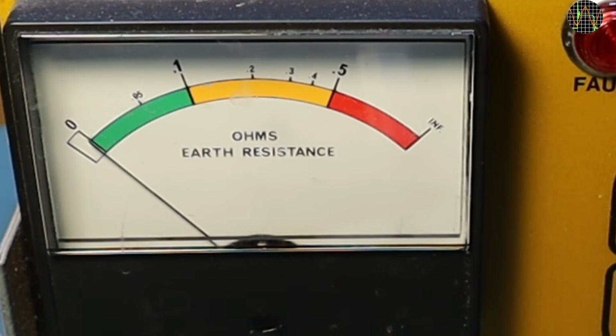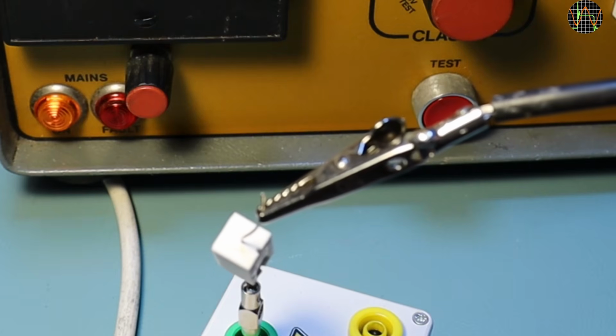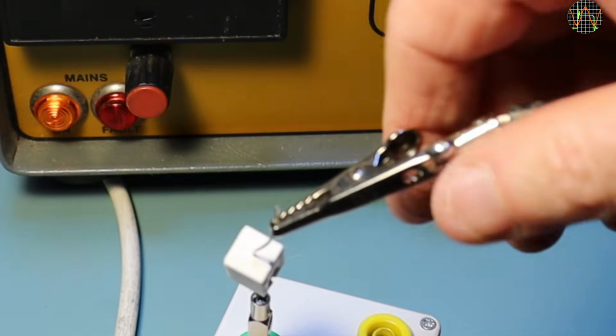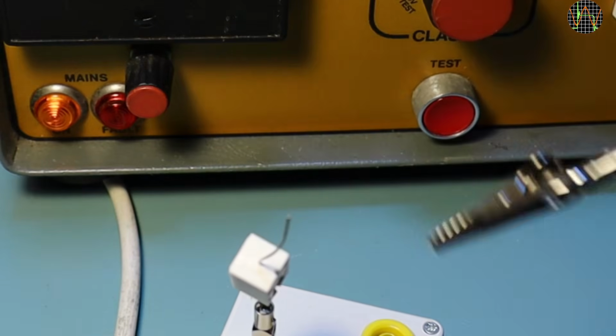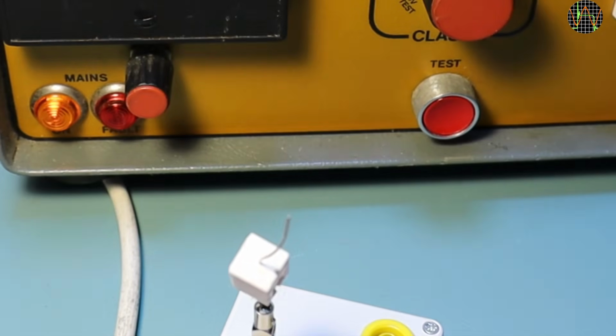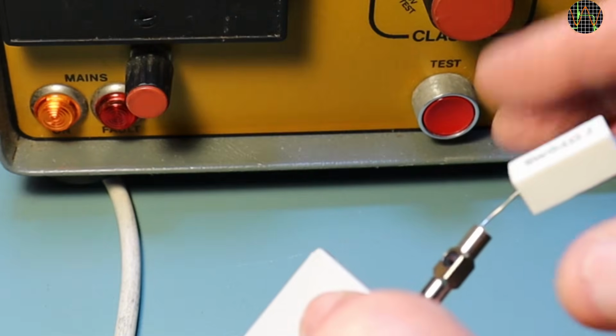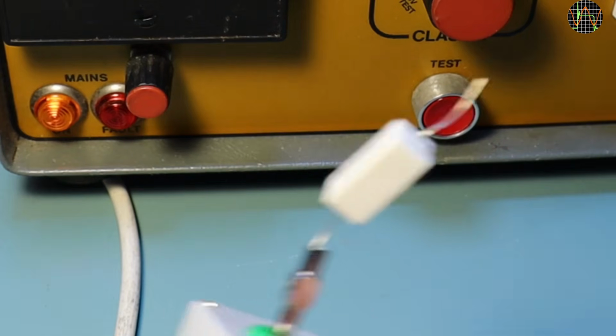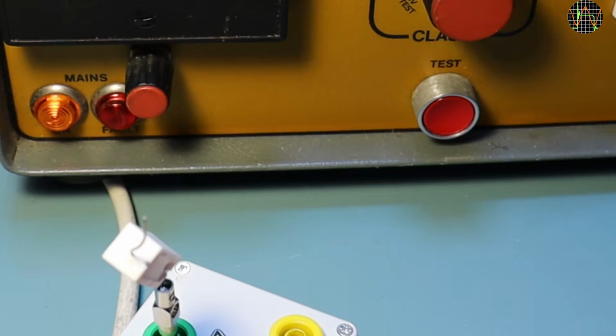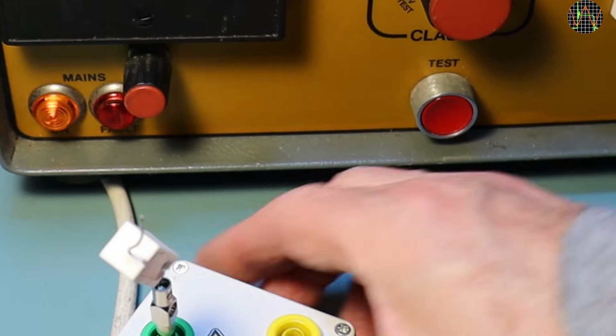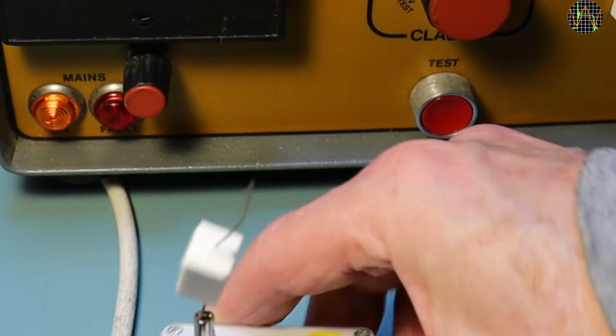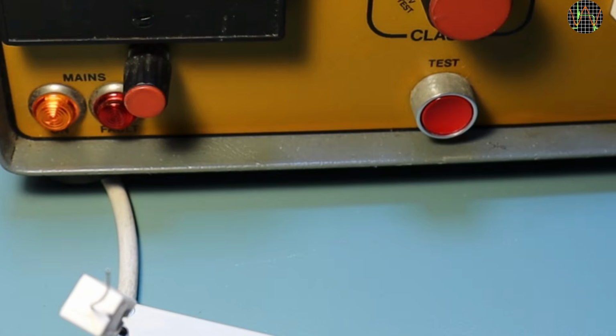But why is this a bad idea? If you would have been in the room, you would have noticed the bad smell of overcooked resistor. That poor 0.1 ohm ceramic resistor is rated for 3 watts. With 32 amps flowing through it, it dropped of course 3.2 volts, and 3.2 volts times 32 amps means it was loaded with 102 watts. You have seen how long I used it, and in that short time it is now literally toast. Even though it still looks okay, it's for the bin.